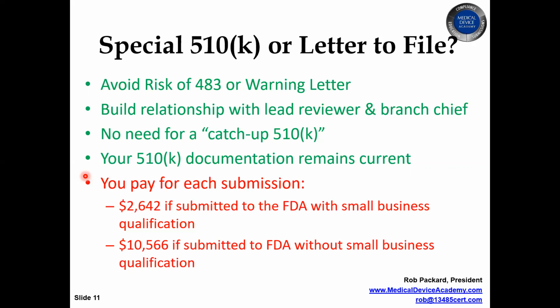So if you don't do a 510K and you do a letter to file, and you continue to do this multiple times, and the FDA doesn't agree with what you found, number 1 possibility is you get a 483. Number 2 possibility is you get a warning letter saying that you need to submit a 510K. And oftentimes the company will be given some leniency and they won't have to pull the product off the market, but they're given a very short leash and expected to submit a 510K right away.